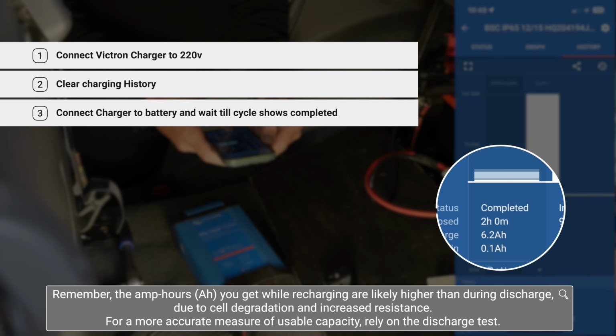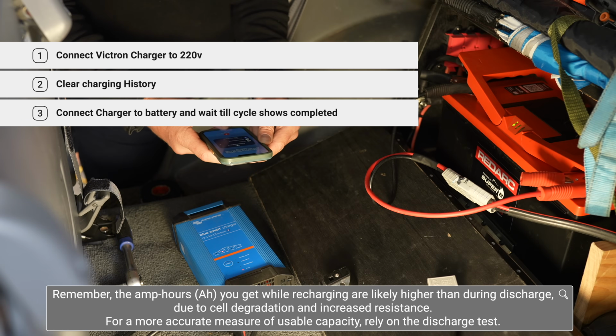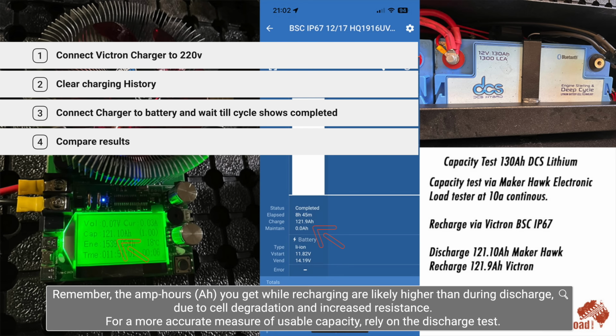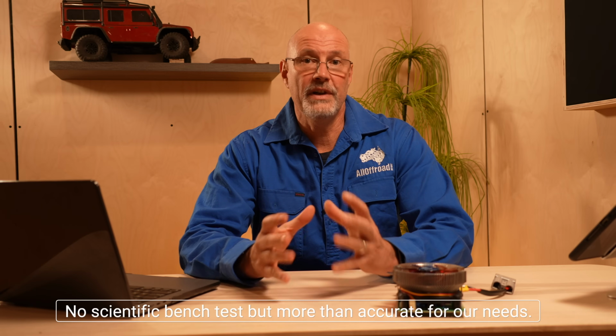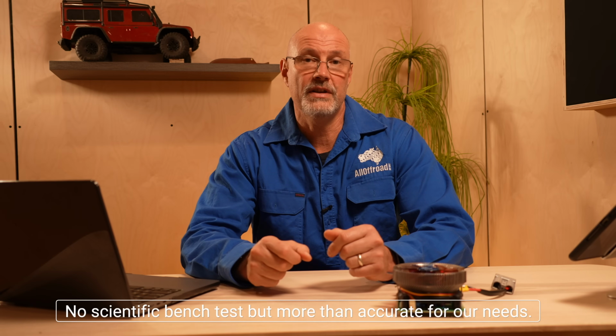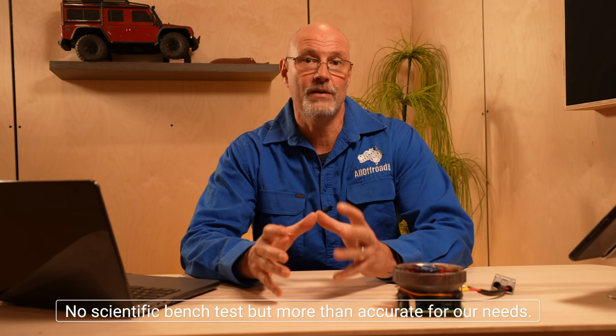If your numbers from the discharge and recharge test are within 2 to 3%, you can be quite certain that you have pretty accurate results. So that's how we do pretty accurate capacity tests to see whether the batteries are still working as they should.